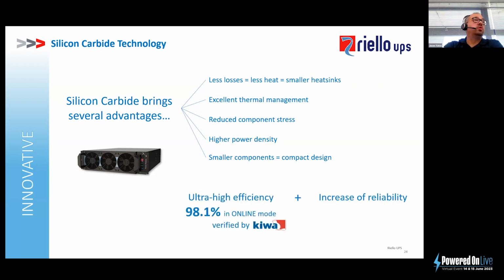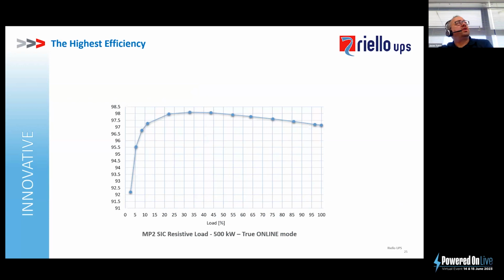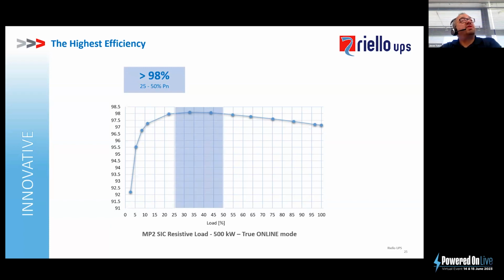Now that particular power module there, again, it's ultra high efficiency, running at 98.1%, and that's been independently verified by Kiwa. Now the benefit again of this is an increase in reliability because of the changes in the components. If we actually look at the performance, this is a typical performance graph of a 500 kilowatt system, which is operating with silicon carbide devices. And as you can see, the system is operating greater than 98% for a load range of around about 25 to 50%.